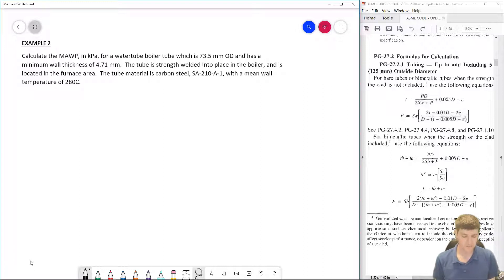So here's our example number two. Calculate the MAWP, the maximum allowable working pressure, for a water tube boiler tube which is 73.5 millimeters outside diameter (OD) and has a minimum wall thickness of 4.71 millimeters. The tube is strength welded into place in the boiler and is located in the furnace area. The tube material is carbon steel, SA210-A-1, with a mean wall temperature of 280 degrees Celsius.